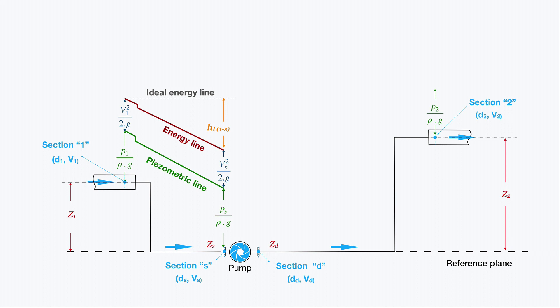Regarding section 2, the pipe where we want to transport the fluid from section 1, we have height Z2 over the reference plane. Energy due to pressure: P2 divided by density multiplied by gravity. And the other term to consider is, of course, the kinetic energy. We also need to take into account the pressure losses, because between section D, the discharge flange of the pump, and section 2, energy losses HL between D and 2 will occur.